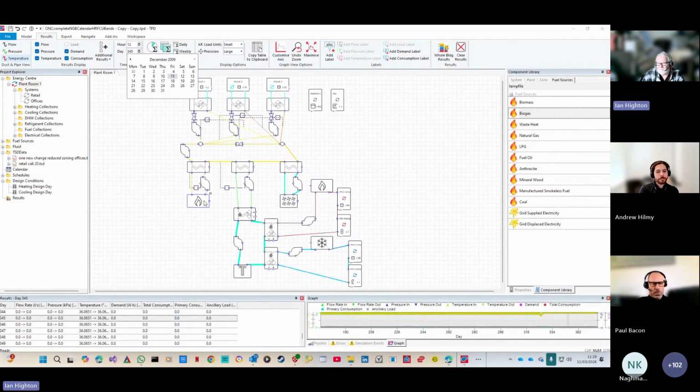But again, Paul, you've made this point, which is when the building was first commissioned, and obviously it wasn't up to temperature, they'd have needed those boilers big style. So it's that initial getting the building up to speed. Things like COVID as well. When the building's completely empty, they may have needed it to preheat after that. So yeah, it's a sort of fail safe, but when we were modeling this, it was quite fascinating to see that these things never actually turned on, which is kind of cute.